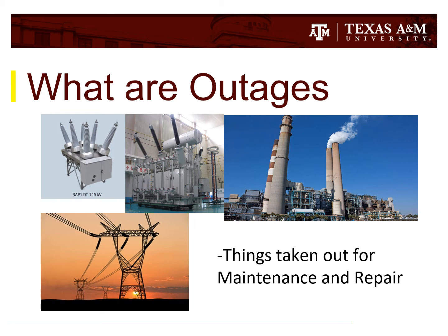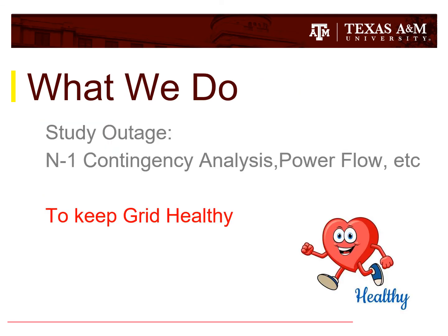So what outage coordination does is we run studies to help mitigate the impacts of these equipments being offline. And we do that by doing N-1 contingency analysis, power flow studies, etc. And this is all done to keep the grid healthy, to prevent blackouts, brownouts, load shedding, what have you.